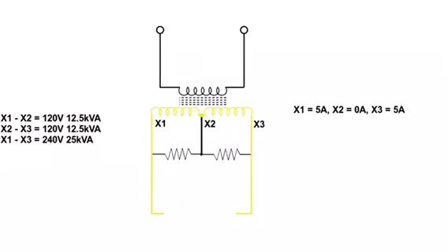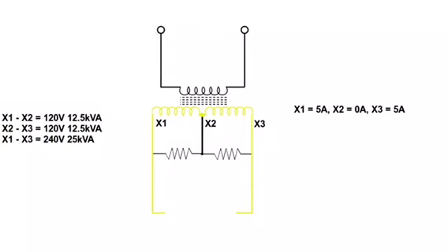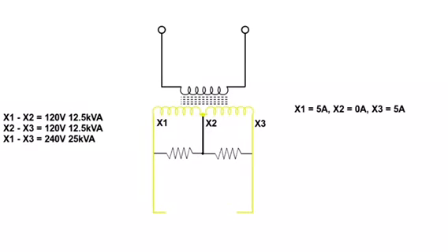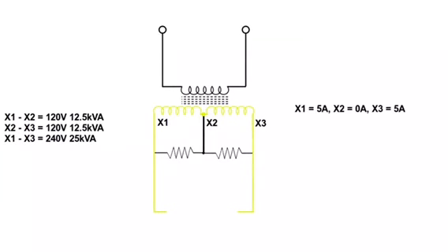Here I've added a second 120 volt load in between the X2 and X3 terminals, X2 being neutral, X3 being line 2. Now this is quite interesting, because now we have two 120 volt loads that are technically connected together in series across a 240 volt coil.